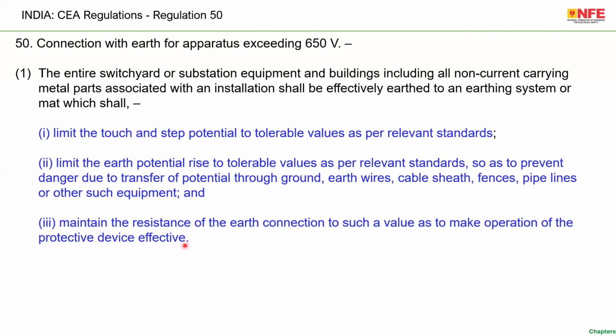Example, the earth electrode resistance in dry condition is 10 ohm. During rain season, it is 2 ohm or 3 ohm. Such changes should not happen, or such changes should not affect the disconnection operation of the protective device. That is the requirement of sub-regulation 1 of regulation 50. So the regulation is very clear and it is the best regulation, I would say. Limit the touch voltage: the first sub-regulation, nobody gets shocked. Second sub-regulation, nothing in the consumer premise or nobody in the vicinity gets a shock during this time, and maintain the resistance so that the protective devices are operating properly.